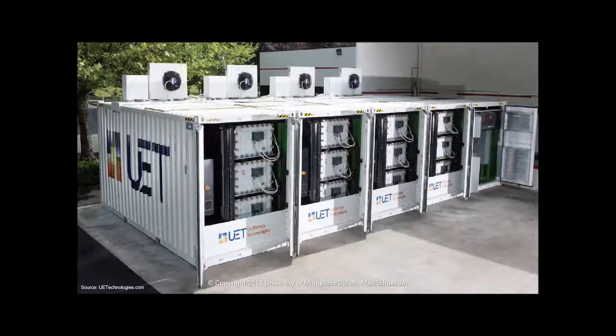And here's a picture just to see what such a system would look like. These are 4 half shipping containers, and always 2 containers have the electrolyte for the vanadium 5+ charge, and the other ones have the electrolyte stored for the vanadium 3+ charge. And the 5th container is the cell, where everything is cycled through. Just to give you a proportion of what such a system would look like, this is 2 megawatt-hours and 600 kW of power.